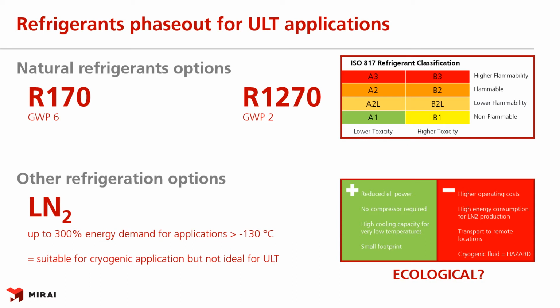Let's have a look at some pros and cons. Pros. Liquid nitrogen requires lower power due to, for example, a missing compressor. It has high cooling capacity for very low temperatures. And the machinery itself has a small footprint, but this depends on the size of the liquid nitrogen tank. Cons. Higher running costs. Liquid nitrogen has very energy-demanding manufacturing procedures. It has to be transported to the site location on a periodical basis. And not to forget, it is a cryogenic fluid which is not very kind to living things. All things considered, is liquid nitrogen ecological?